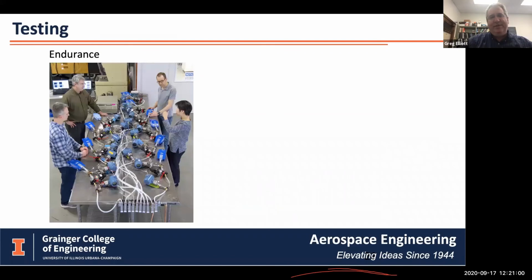For the testing of this device, we set up about 10 of these devices at CTS, with test lungs hooked to them, flow rate control, and monitored them. One of our devices had over 1 million cycles. We did endurance testing to make sure the device would work for several days, up to a week, without failing. And I don't think we had any of them fail. Every once in a while, we would have to readjust some of the rate adjustments, but otherwise they performed very well. Our final design did.